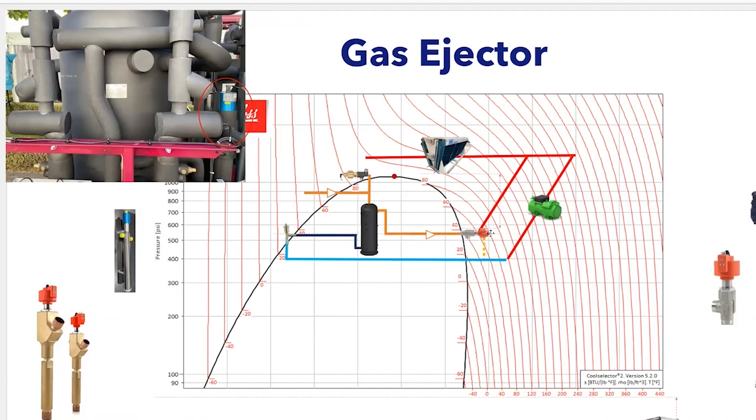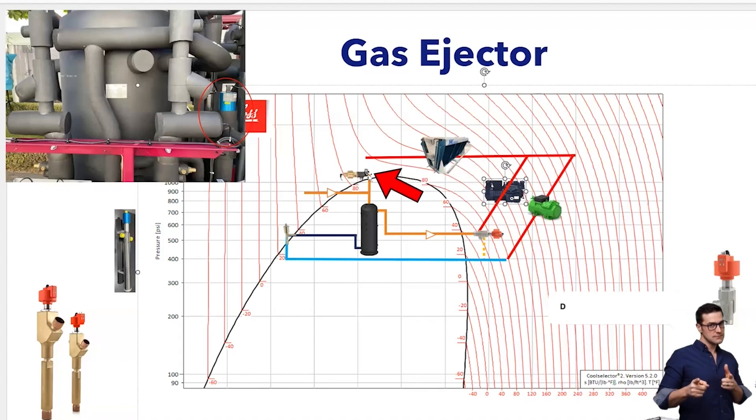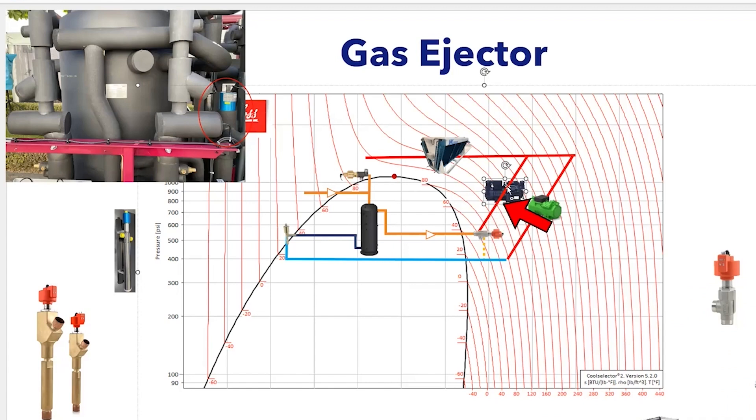Now with the ejector and parallel compression, you'll have a parallel compressor. The medium temp goes through our gas cooler condenser, comes down through our throttling valve, our high pressure valve into our flash tank. When it's really warm out, this gas will go through the parallel compressor.